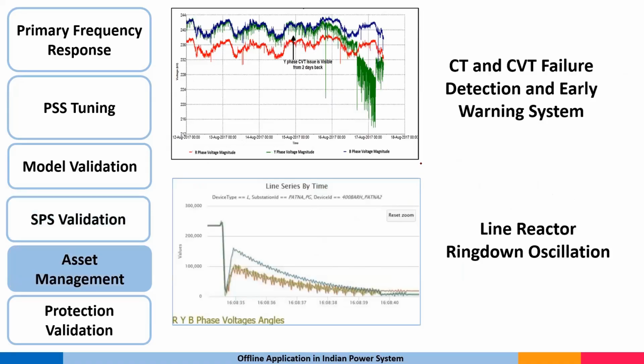Then there may be an issue with any CT or CVT, because you know that the initial input for the phasor estimation of current and voltage is from CT and PT. So any problem with the measurement device itself will be reflected in the PMU data. That also we have seen. We have seen a problem with the CVT itself. Voltage data was coming and the CVT was providing erratic information.